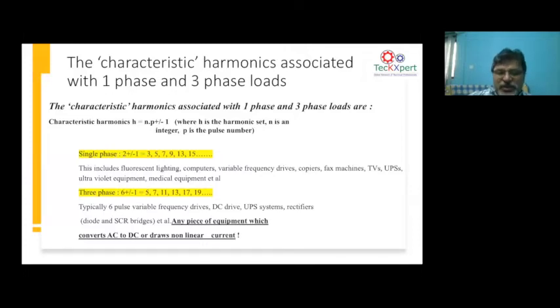Now when you look into this 4 diode and 6 diode, the characteristic harmonic equation tells you the harmonic produced by a power electronic device is related by the simple formula NP plus minus 1, where N is any number and P is the pulse number. For example, let us take the NP plus minus 1 equation to understand a single phase electronic load. As I told you, a single phase electronic load, whether a fax machine, lighting, or a computer, has 4 diodes.